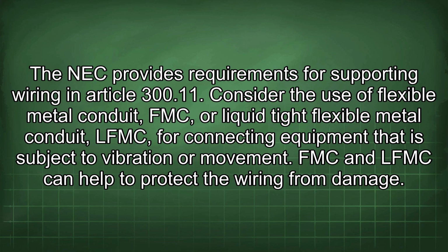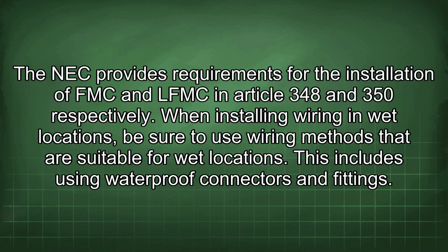Consider the use of flexible metal conduit (FMC) or liquid-tight flexible metal conduit (LFMC) for connecting equipment that is subject to vibration or movement. FMC and LFMC can help to protect the wiring from damage. The NEC provides requirements for the installation of FMC and LFMC in Article 348 and 350 respectively.